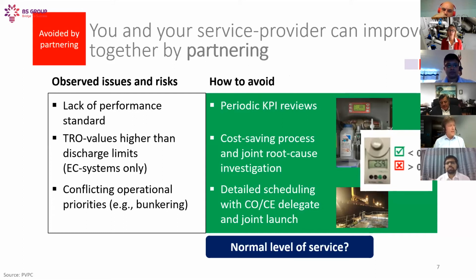We've identified that in many cases we measure too high TRO values, specifically for electrochlorination systems, and the reason is often the TRO sensors. Many service providers continue the whole VGP monitoring procedure even when TRO is too high, which causes a lot of extra costs. If you have a procedure in place to investigate the root cause of the TRO sensor calibration issue, and an agreed procedure to stop the rest of the work when TRO is too high anyway, you avoid a lot of unneeded resources.